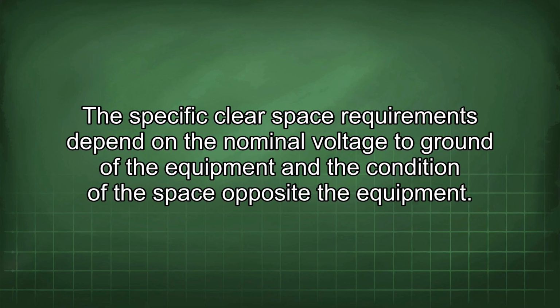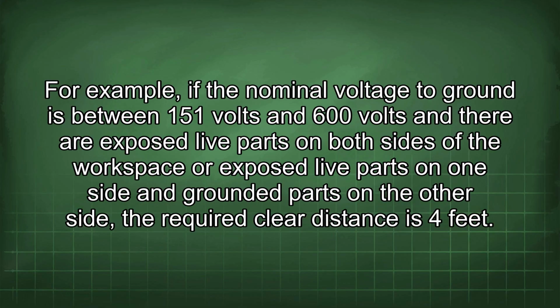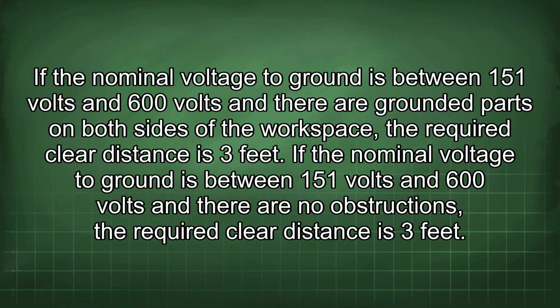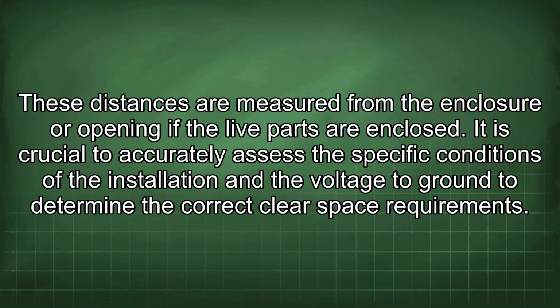The specific clear space requirements depend on the nominal voltage to ground of the equipment and the condition of the space opposite the equipment. For example, if the nominal voltage to ground is between 151 volts and 600 volts and there are exposed live parts on both sides of the workspace, or exposed live parts on one side and grounded parts on the other side, the required clear distance is 4 feet. If the nominal voltage to ground is between 151 volts and 600 volts and there are grounded parts on both sides of the workspace, the required clear distance is 3 feet. If the nominal voltage to ground is between 151 volts and 600 volts and there are no obstructions, the required clear distance is 3 feet. These distances are measured from the enclosure or opening if the live parts are enclosed.